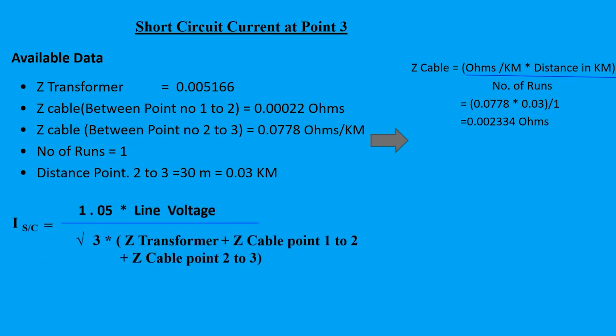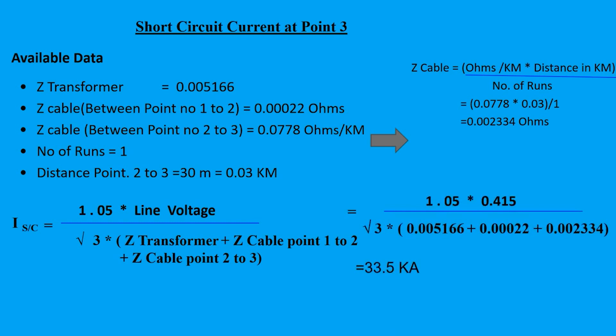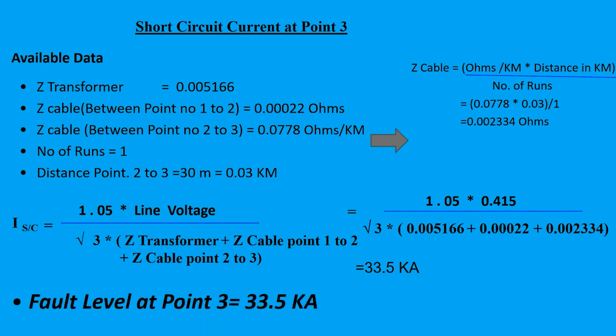ISC equals 1.05 times the line voltage, all divided by root 3 times Z transformer plus Z cable point one to two plus Z cable point two to three. That gives us 1.05 times 0.415, all divided by root 3 times 0.005166 plus 0.00022 plus 0.002334, which comes to 33.5 kilo amperes. So the fault level at point number three is 33.5 kilo amperes.